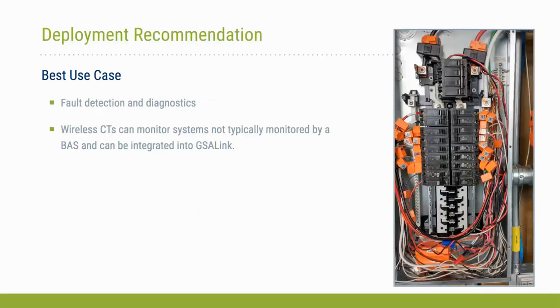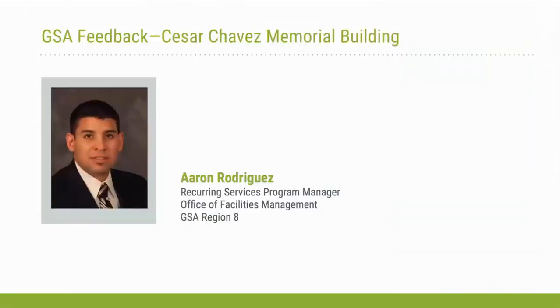Some deployment recommendations: we identified two best use cases. Fault detection and diagnostics would be a great use case, as well as augmenting the capabilities of GSA Link. If a system isn't already connected to the BAS, for example lighting equipment not part of the BAS system, the wireless CT can monitor and provide information on that load.